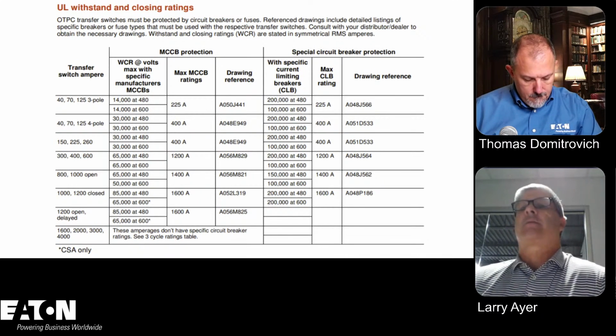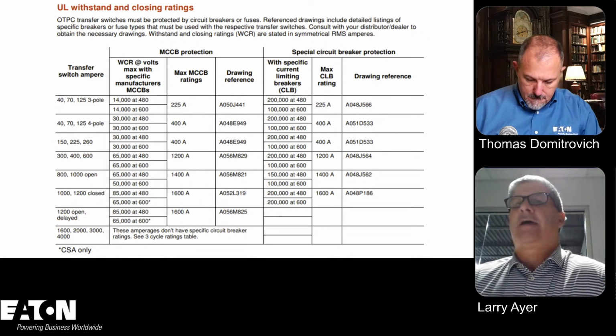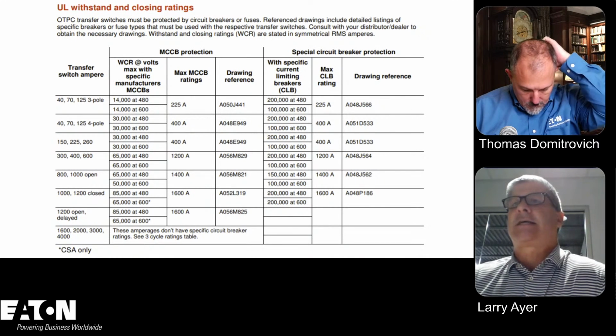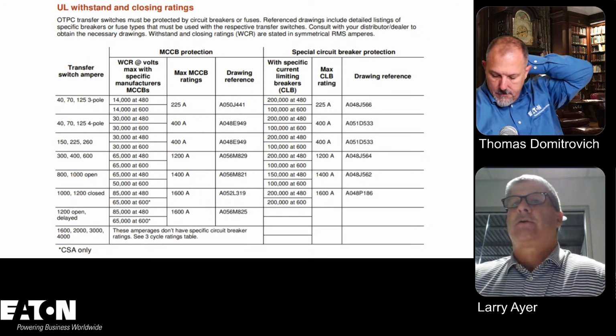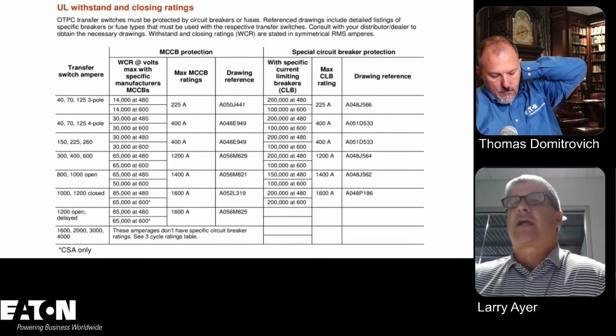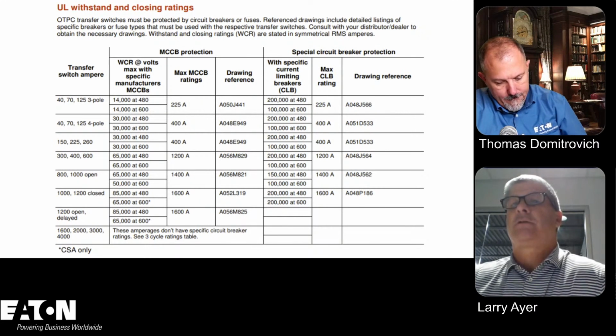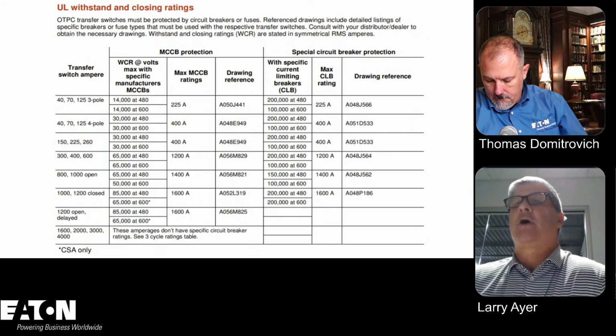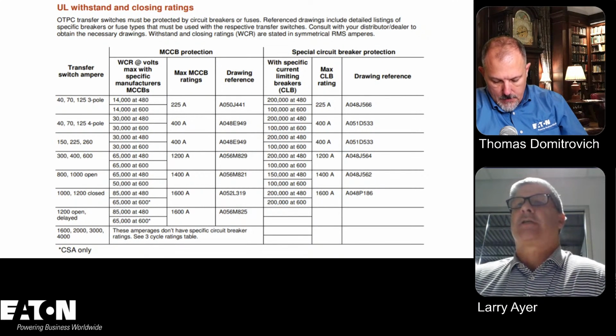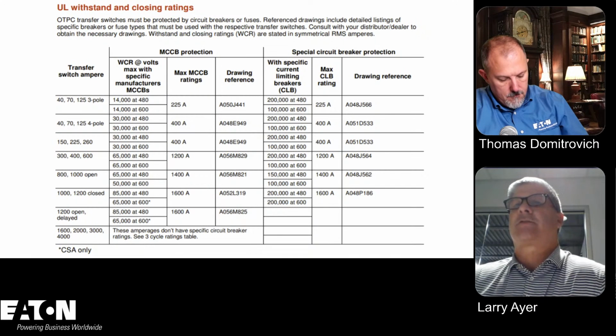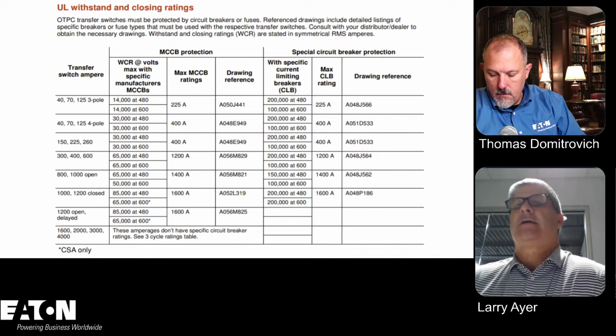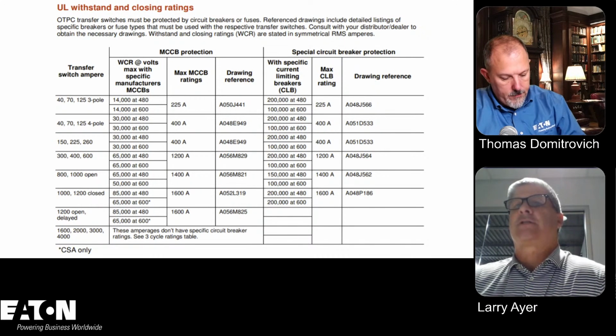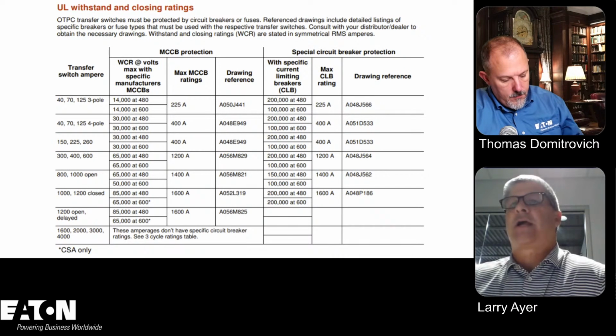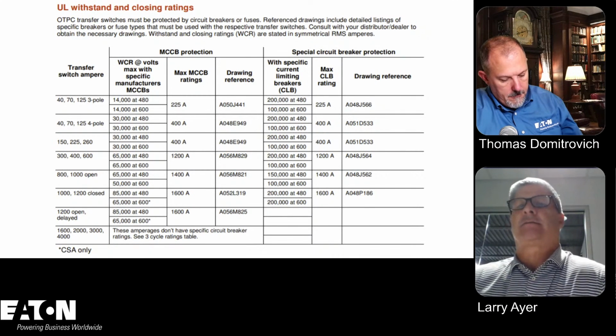So now, if for some reason you had to have an overcurrent device at 6 times the motor, you would then have to bump that transfer switch up to the next row. So even though you had a 200 amp motor, you could say, okay, I'm going to pick that transfer switch, and it says it is only protected up to 400 amps. I would have to go to the next one and buy maybe a 400 or 600 amp switch with a 1200 amp maximum rating to be able to satisfy the NEC.